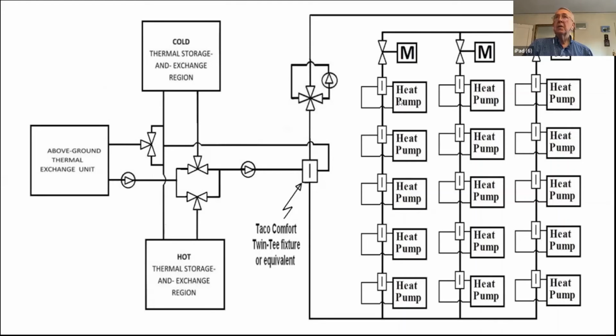Because if we're, let's say, in a heating condition, then every one of these heat pumps is taking heat out of the water, and it's making the water colder as it flows down this path. So the bottom heat pumps will always be getting the worst temperature for efficiency. The top ones will always be getting the best temperature for efficiency. That's really not fair, and it might cause failure of some of the heat pumps.